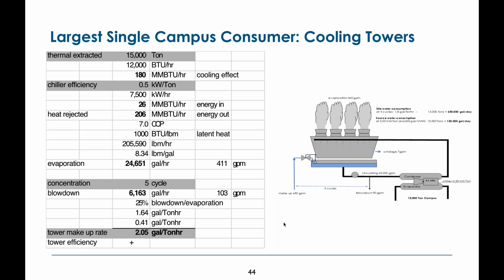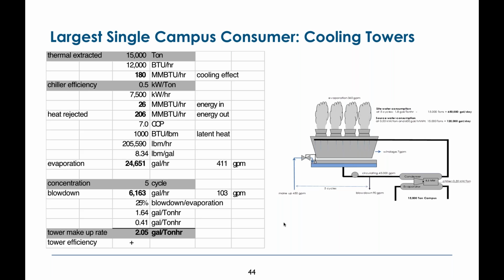So at the bottom of this, at 5 cycles, that represents 25% of the water you're evaporating is now being wasted in order to hold 5 cycles. It's pretty typical in the Southwest that we run at 5 cycles, maybe a little lower than that, which gives us a total makeup rate of 2 gallons per ton hour, which is kind of an interesting number when you think about gallons of milk and ton hours of air conditioning. It's a fair amount of water that you don't see. It's invisible, not really an obvious part of air conditioning.